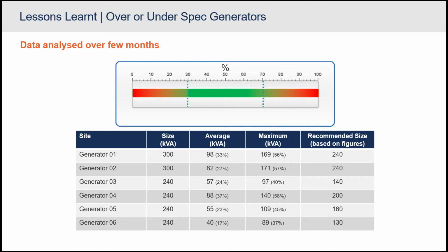So there are a few things we can see from here. We can recommend a replacement asset when we get to that point in time. When we replace that asset, most of the time clients replace it like for like - if they had a 240 in there, they'll put in a 240 again if they don't have the information to look at it. So here, for instance, we would recommend a smaller generator, which reduces your capital outlay, but also reduces your fuel consumption and your maintenance cost. It really snowballs to have the right generator selected for your application.